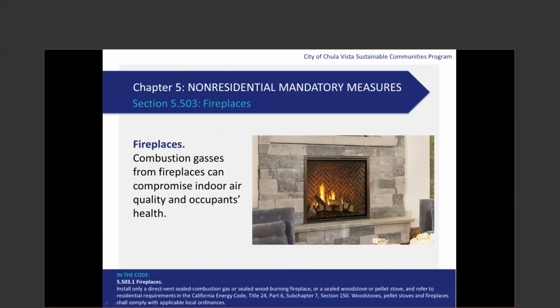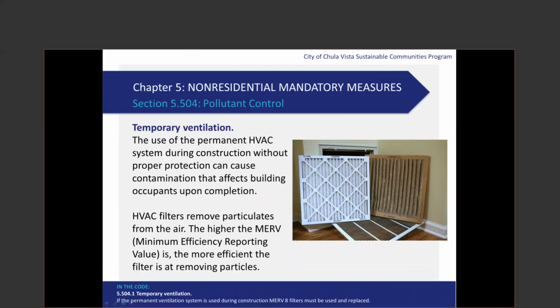Due to the dangerous gases and air pollution from fireplaces, CalGreen requires any installed gas fireplace must be direct vent sealed combustion type. This effectively prevents indoor air from being involved in combustion or exhaust of the fireplace. To prevent dust and debris getting into permanent HVAC systems used during construction, a minimum MERV 8 filter must be installed. And before occupancy, it must be replaced, this time with a MERV 13 filter, as you'll see in the later section and as required in the Energy Code.